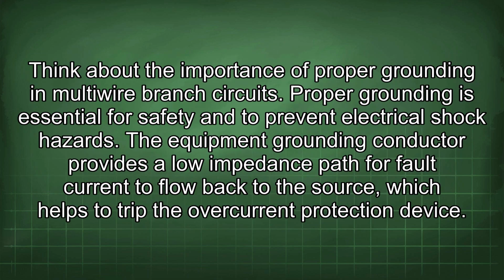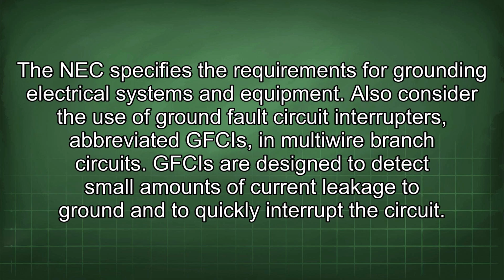Think about the importance of proper grounding in multi-wire branch circuits. Proper grounding is essential for safety and to prevent electrical shock hazards. The equipment grounding conductor provides a low impedance path for fault current to flow back to the source, which helps to trip the overcurrent protection device. The NEC specifies the requirements for grounding electrical systems and equipment.